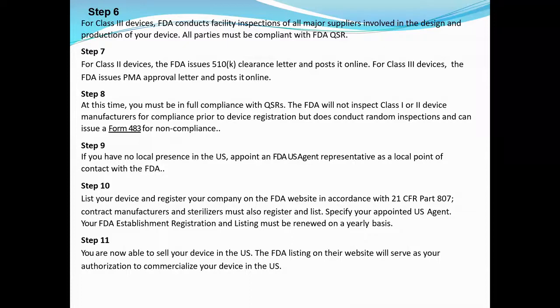Please keep in mind, after following all the above 10 steps, you are now ready to sell, you are now able to sell your device in the US. Once you get the marketing approval, everything is done, then you are ready to market. So the FDA listing on their website will serve as your authorization to commercialize your device in the US. So I hope you understood the US FDA in brief: how it is categorized, how the predicate device is selected, and how the 510K application is prepared. Then which category comes under PMA, which category comes under 510K, how we apply, how the FDA comes for the audit and inspection. Then we have to follow the quality management system, QSR as per 21 CFR Part 820. Your firm has to be registered. So all these things are very, very important when you are dealing with USFDA.